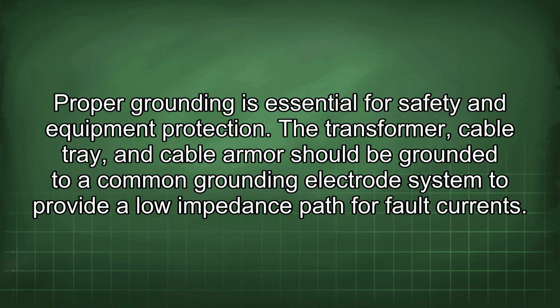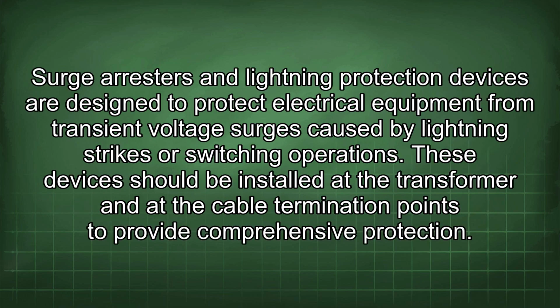Proper grounding is essential for safety and equipment protection. The transformer, cable tray, and cable armor should be grounded to a common grounding electrode system to provide a low-impedance path for fault currents. Surge arresters and lightning protection devices are designed to protect electrical equipment from transient voltage surges caused by lightning strikes or switching operations. These devices should be installed at the transformer and at the cable termination points to provide comprehensive protection.